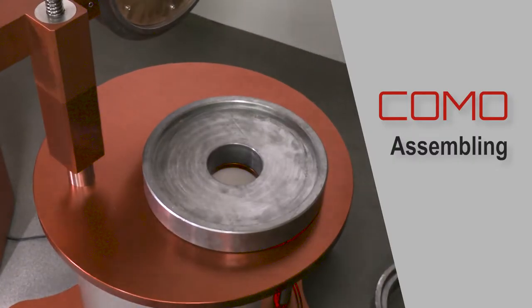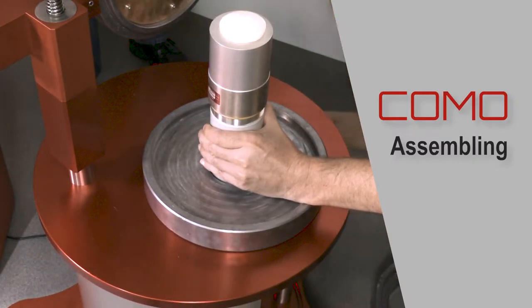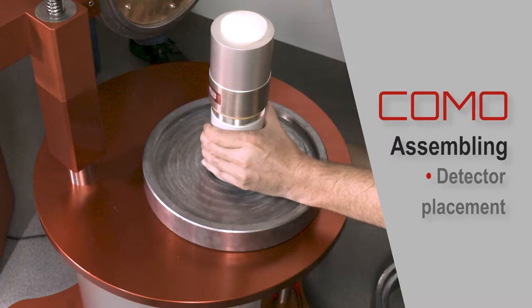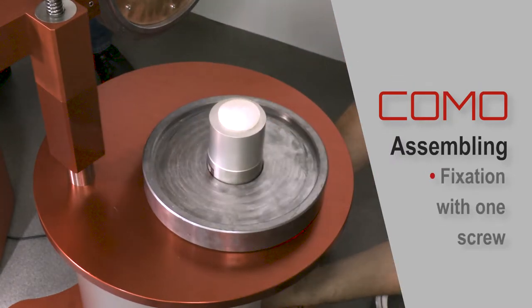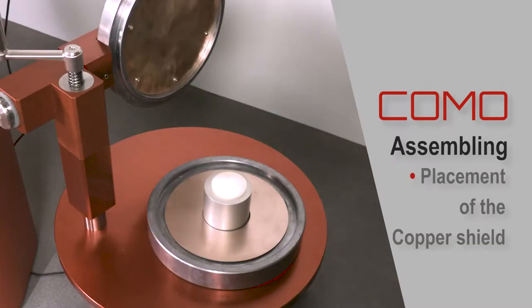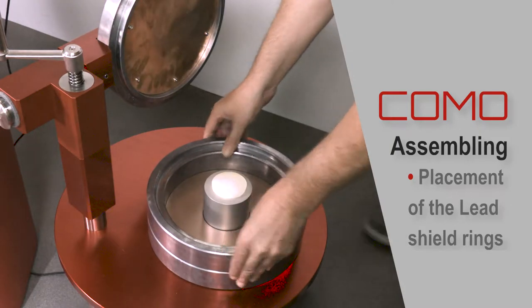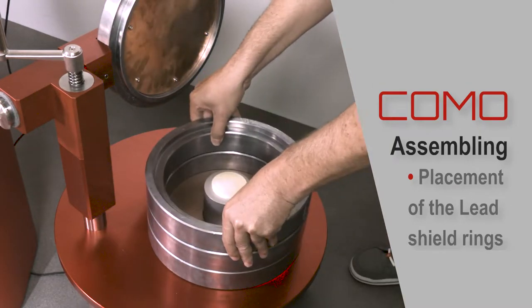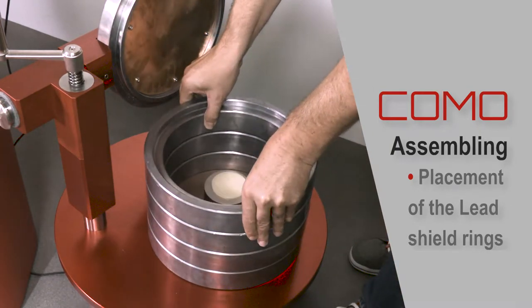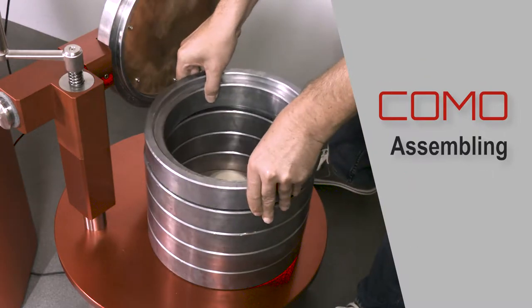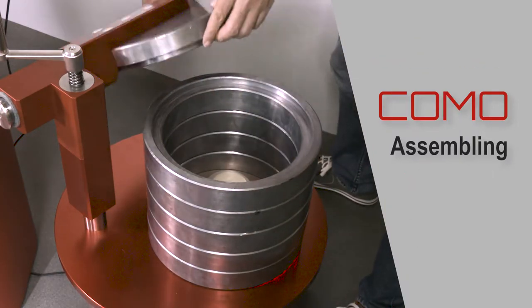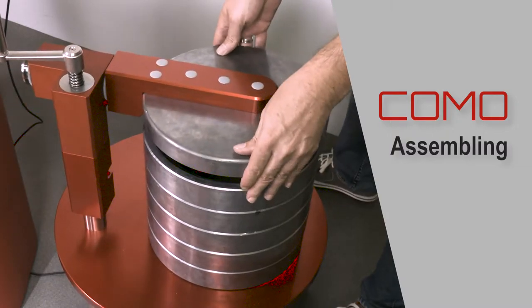It's very simple to place the detector inside the measuring chamber. You fix it with one screw underneath, place first the copper shield and then simply take one ring after the other of the lead shielding. That gives you also a possibility, if you had a contaminated sample, to clean it very well. That was it.